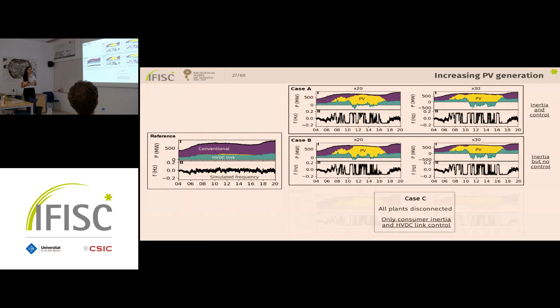So yeah, once we have validated the model, we can use it to analyze different scenarios. And we focus on increasing photovoltaic generation, as I said. So we will be comparing 3 different cases depending on what we do with the conventional power plants once they are no longer needed. And we will be comparing those to this reference case where we have the power mix and the simulated frequency. So in case A, we will always leave one power plant working at a minimum power so that it provides inertia and control. In case B, all power plants will stay connected even when they don't provide any power, but just to provide inertia. And in case C, we will disconnect completely all the power plants so that they don't provide inertia and control, and the only inertia and control left in the system is that from consumers and the control from the high voltage DC link.